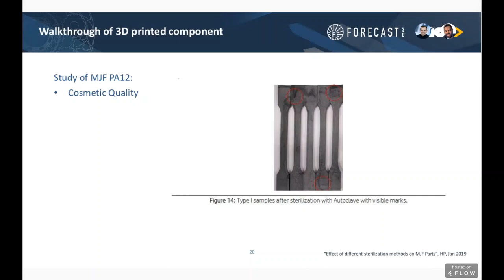The last thing that we consider here is the potential for the part to absorb any materials. And this is just a sample of what those results could look like. So in an autoclave, when it's steam and heat oriented, you're going to see a little bit more potential for gaining material or absorbing some water. The formaldehyde is in a similar situation, where it's a chemistry that can potentially be added, and you have to assess the risk of these percentages for your application to see if it matters. The other ones you don't see as much of an increase, purely because you're generally just applying energy.